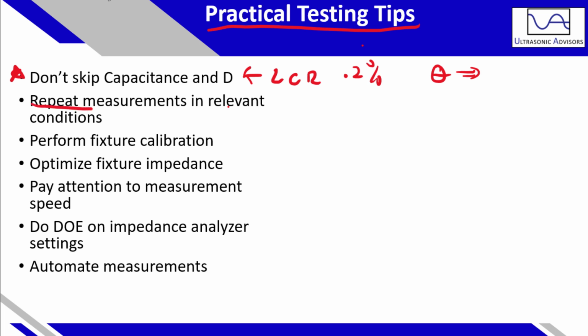Repeat measurements here in relevant conditions. What I mean by repeat measurements is when we start our piezoelectric ultrasonic device assembly, we start with the bare crystal. So do your resonance and capacitance measurements there. The next step, we bond our piezo, or we assemble our device. We bond or assemble, and you need to do measurements at this time as well. Then, if there are any subcomponents, in between the assembly we also do measurements in that case.